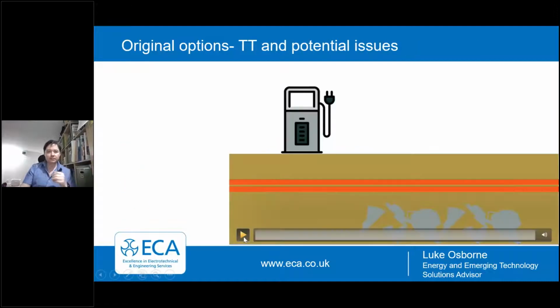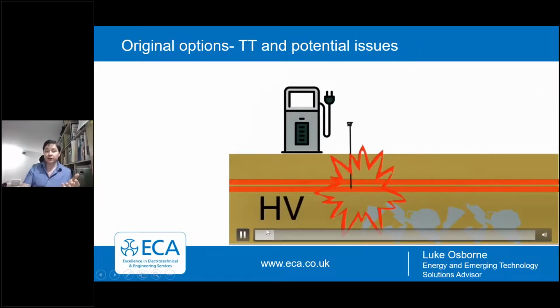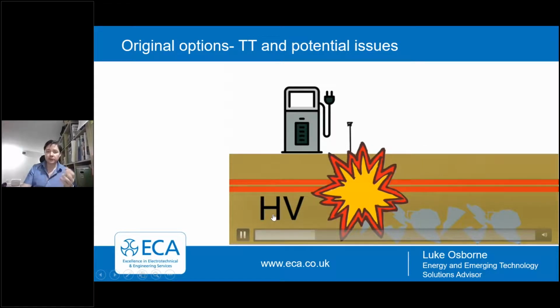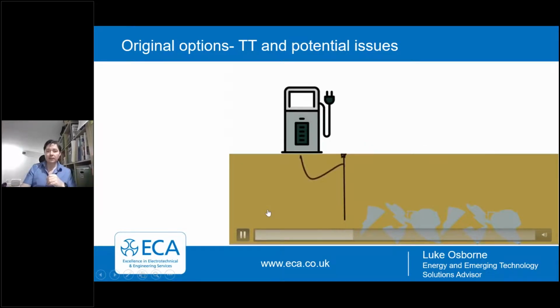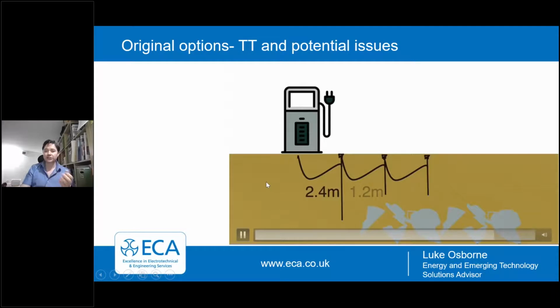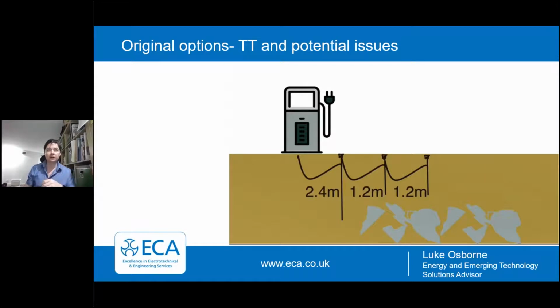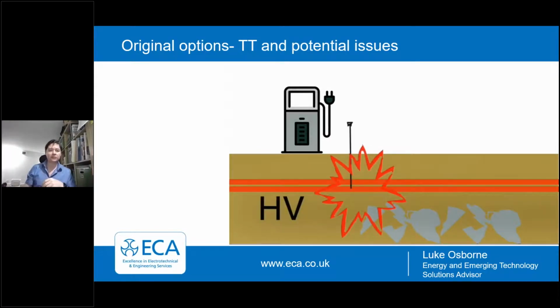So with TT, there are some potential issues. There's the risk of going through HV cables in the ground, which are unbeknownst to the installer. There's also the risk of hitting underground strata, and to reach the resistances needed, you will likely need multiple earthing electrodes, as you can see here. So all three of those are annoying issues. Okay, number one, if you went through an HV cable, that's more than an annoyance, it's a clear health and safety issue. But the risk of ground strikes, having to remove and move and locate your earth rods in different locations, is an onerous time.